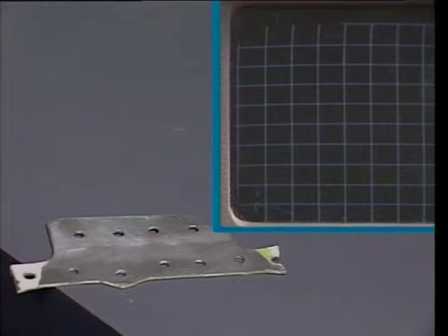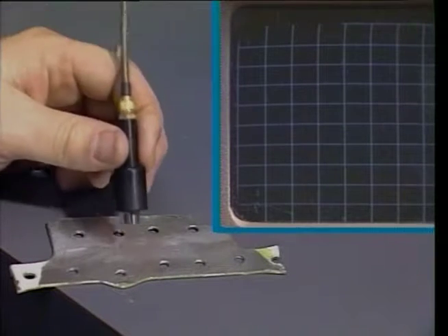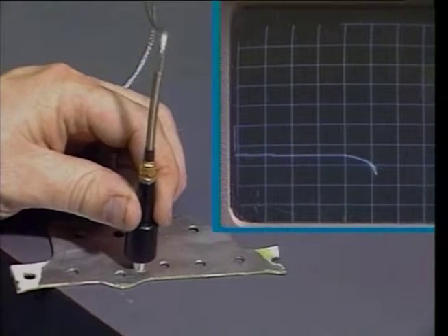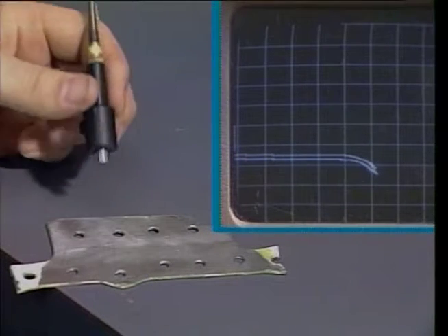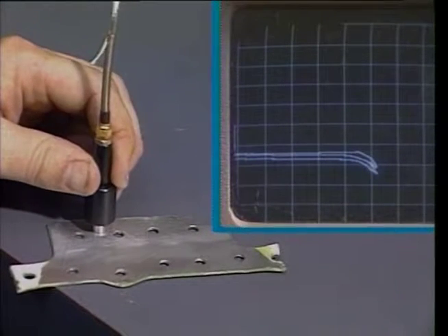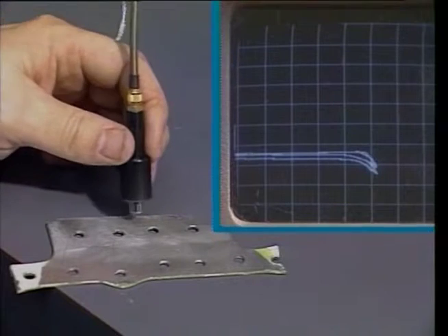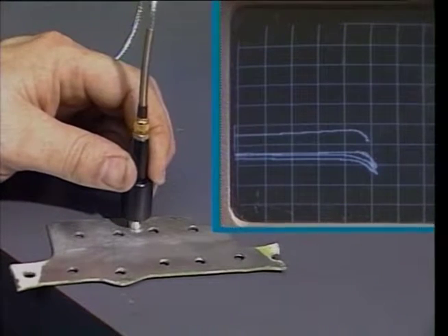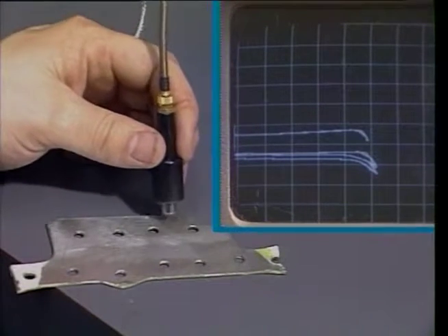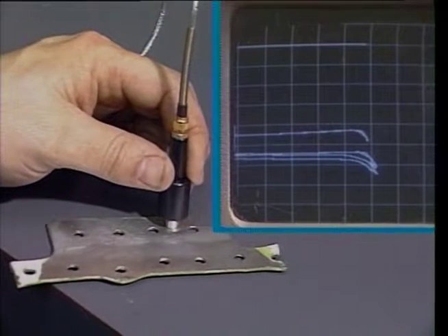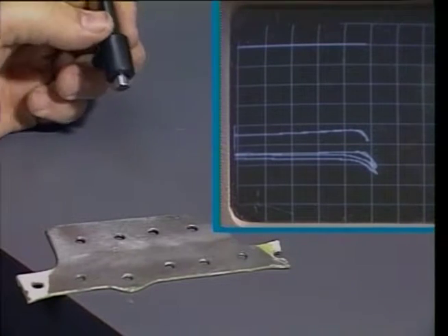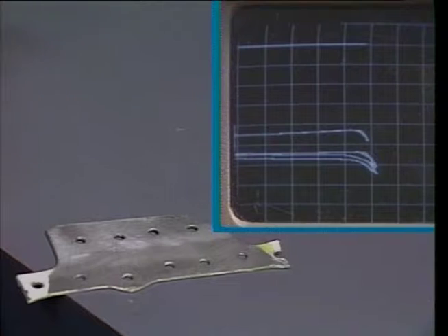This split screen demonstrates the sensitivity of low-frequency eddy current technique in the hands of a skilled technician. First one is the baseline. We got slight material loss. And this one here is approximately 10% material loss. And this one is up off the screen, and when it gets that high, you really don't know exactly what percent, but you know it's getting pretty bad.